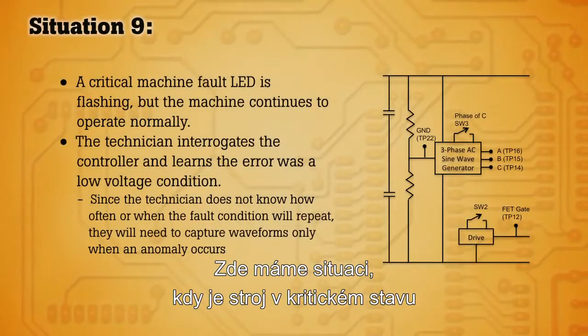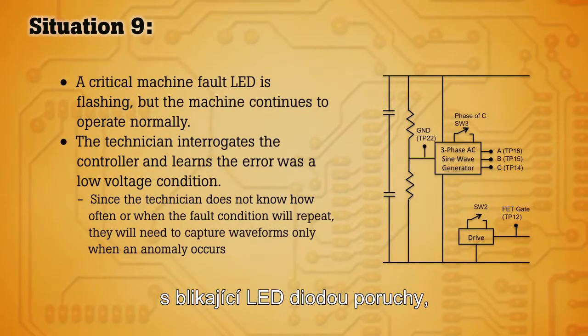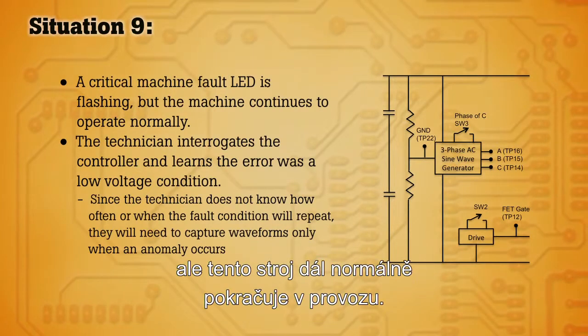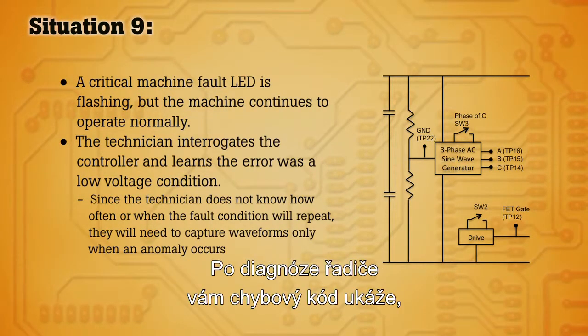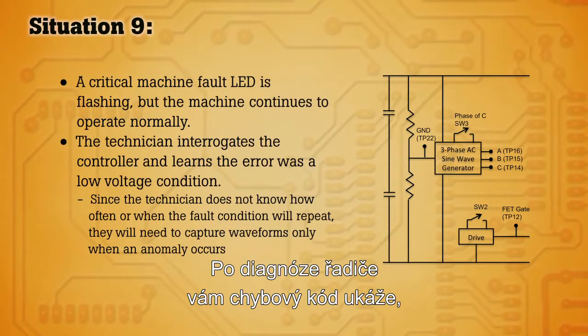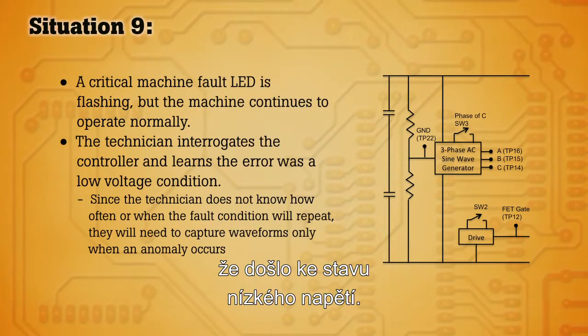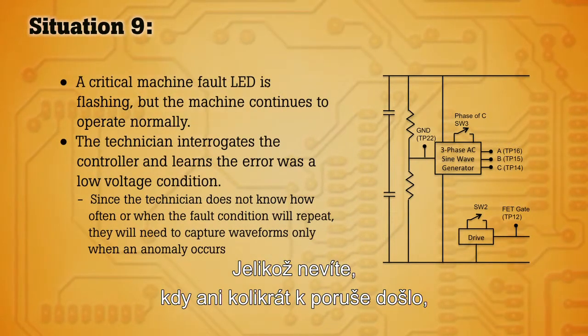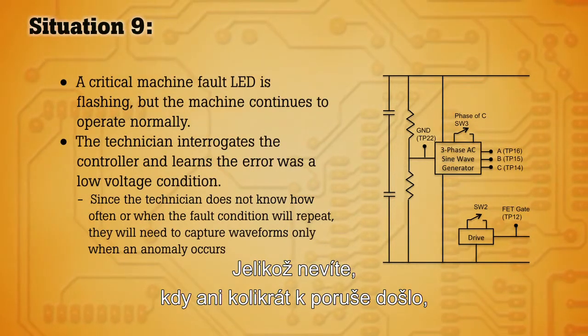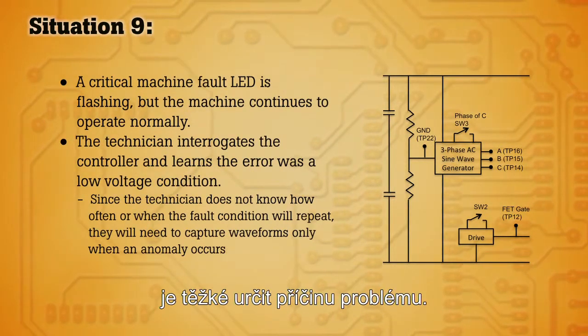Here we have a scenario where you have a critical machine with a fault LED flashing, but the machine is continuing to operate normally. Diagnosing the controller, you find the error codes indicate there has been a low voltage condition. Since you don't know when the fault occurred or how often it's happened, it's difficult to diagnose the root of the problem.